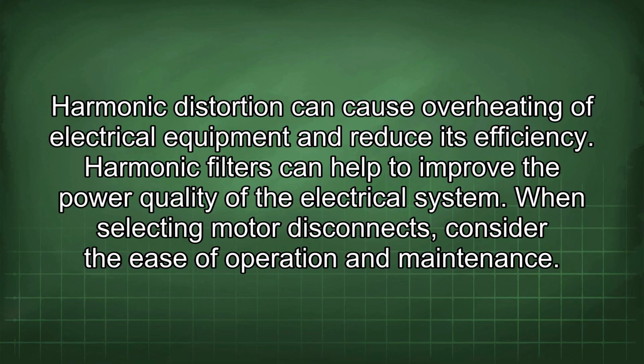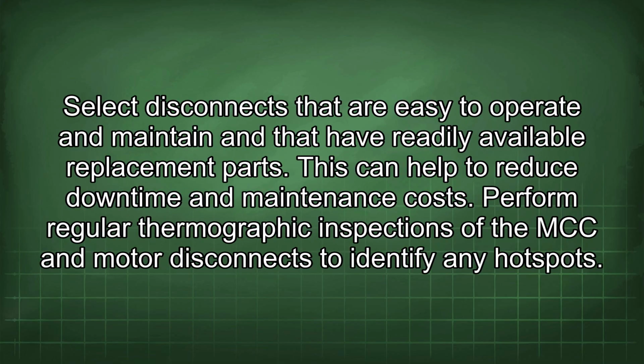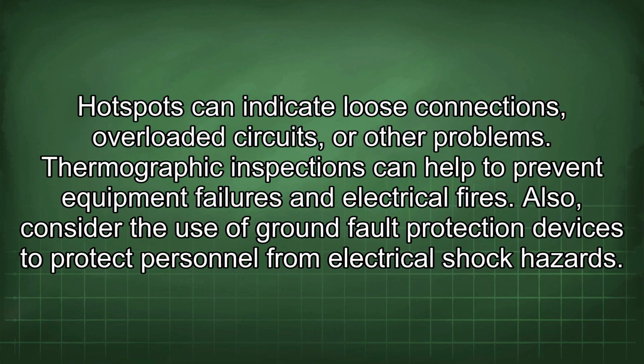When selecting motor disconnects, consider the ease of operation and maintenance. Select disconnects that are easy to operate and maintain and that have readily available replacement parts. This can help to reduce downtime and maintenance costs. Perform regular thermographic inspections of the MCC and motor disconnects to identify any hotspots. Hotspots can indicate loose connections, overloaded circuits, or other problems. Thermographic inspections can help to prevent equipment failures and electrical fires.